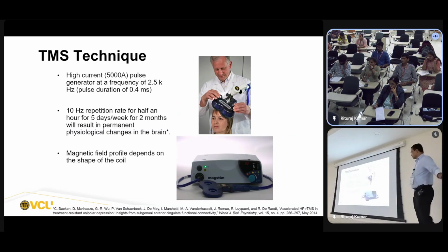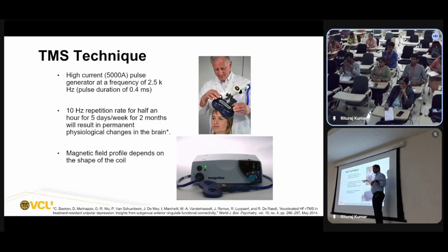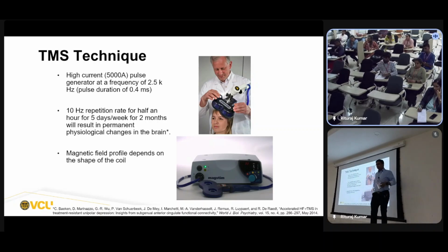That's how TMS works. This is how a coil looks like. This is just copper windings, and it's placed on somebody's head. And the coils look like this. This is used for 1 hour long stimulation because it needs to be cooled. When you do it for 1 hour or 45 minutes, it heats up a little, so you need some cooling fan here. This one is laboratory grade, so you don't need 1 hour stimulation.